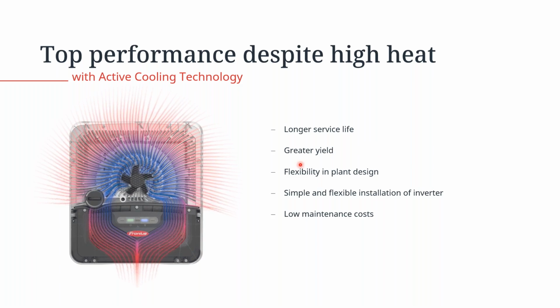In addition to that, we have greater yield because of active cooling. The inverter does not derate even at high ambient temperatures. So in most instances, research has shown that most inverters that do not have active cooling would start derating their power output when the ambient temperature starts going above 30 degrees Celsius. But the Gen24 Plus and the Gen24 are able to operate even at 40 degrees Celsius ambient temperature without derating power output. So it gives you also a lot of flexibility in plant design because of this. So you're not limited even in terms of inverter orientation, in terms of installation. So you can have a vertical, horizontal, or an inclined installation. So you get a lot of flexibility in this manner.